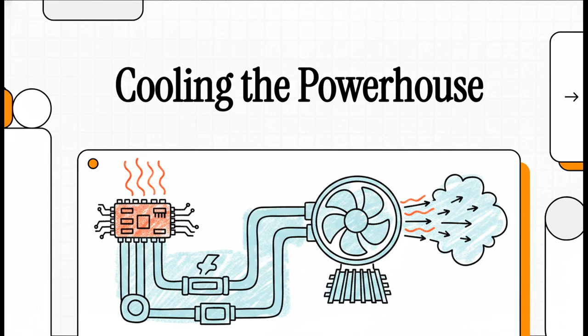To get a sense of the scale here, consider a 1 megawatt industrial drive, that's a million watts, that's 97% efficient, which sounds amazing, right? But it still wastes that last 3% as pure heat. And that adds up to 30 kilowatts of raw thermal energy that has to go somewhere.